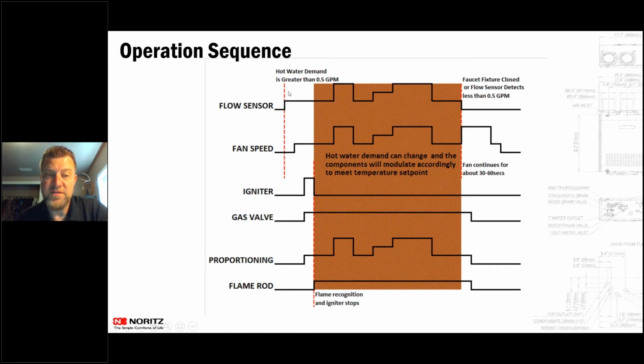Once that flow sensor is triggered, the fan kicks on, the igniter ignites the burner, and the gas valve turns on at the same time, igniting the gas. That gas valve is going to modulate up and down for whatever you have there. Then as soon as the flow rate drops below the minimum, which might be 0.5 gallon per minute to start, but with our units, we can modulate down to 0.24 gallons per minute going through the unit before it'll shut off.